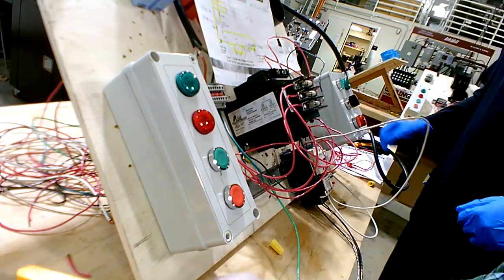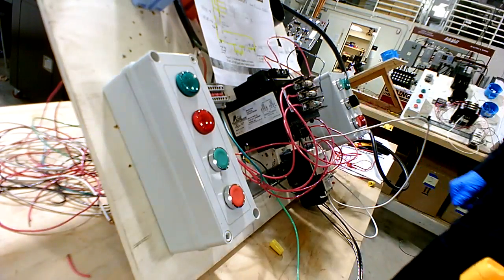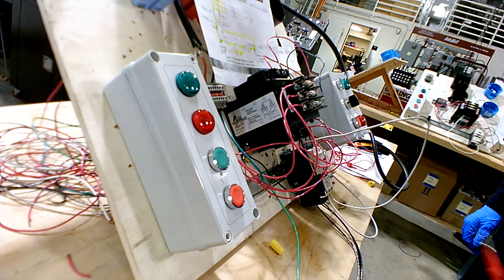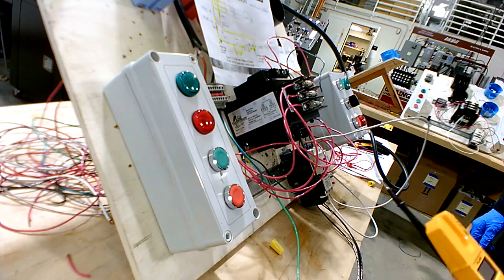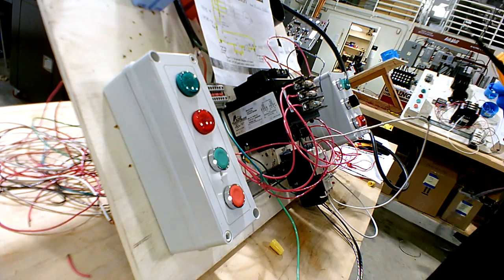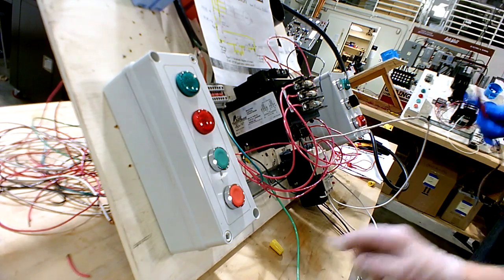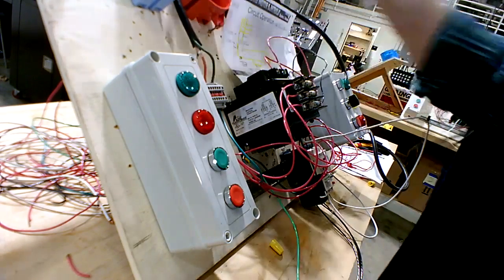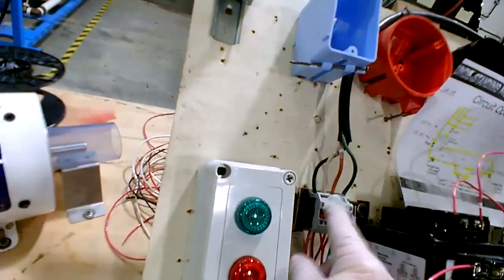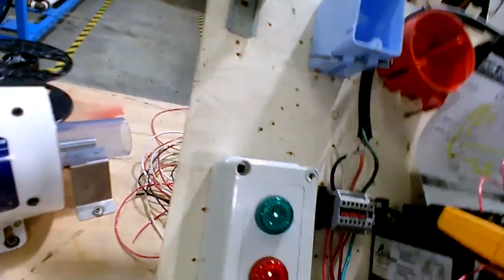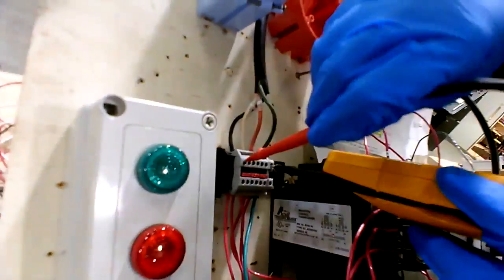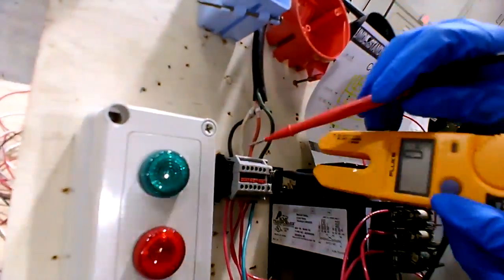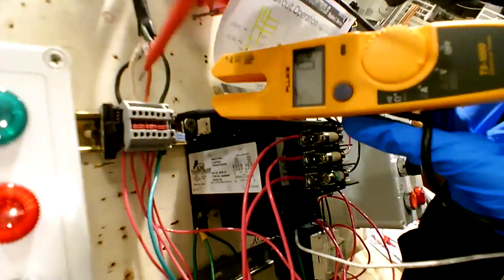And then we're going to test it to make sure it's dead. Put the probe in there like that. You can go up here and check your incoming to make good and sure that it's dead. So you can go from each phase to ground to start. We go to ground and then go 1, 2, 3. Flip your meter around so you can see. So you got a 0.